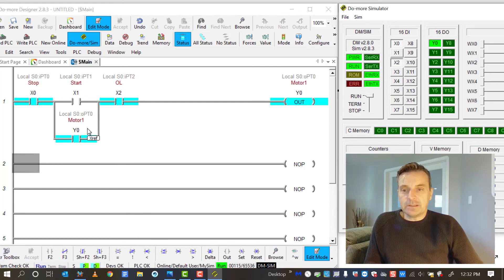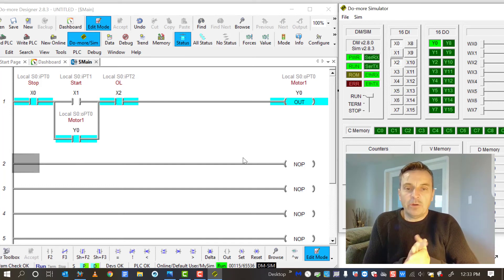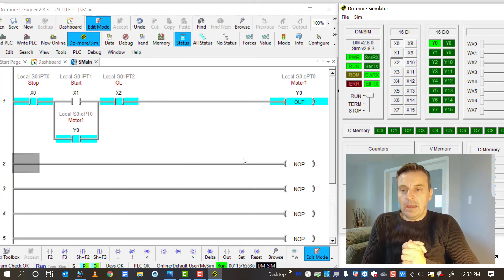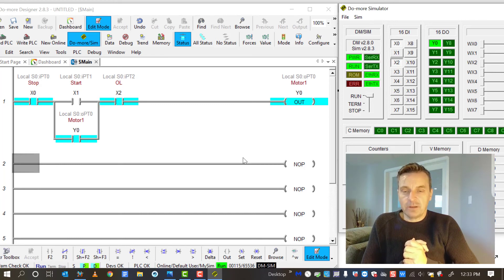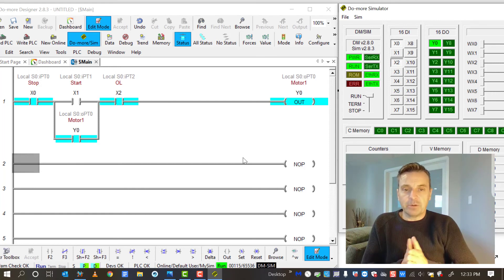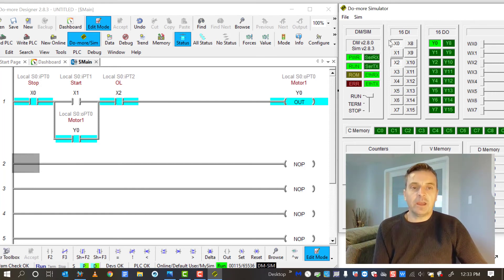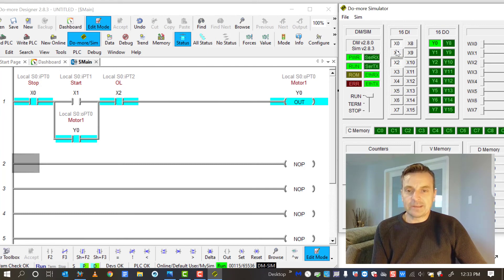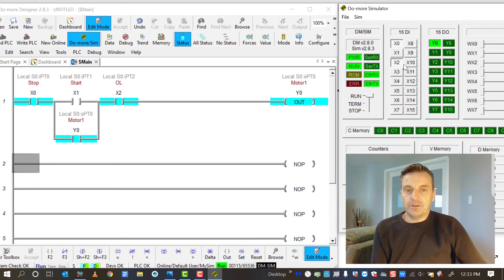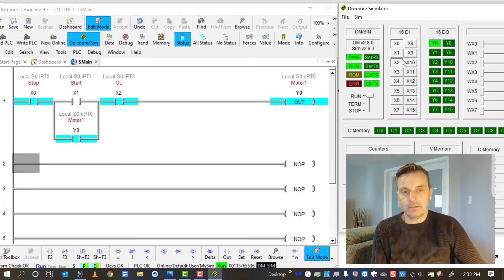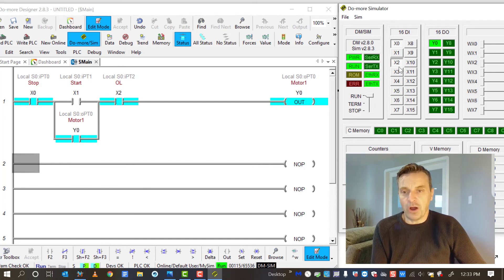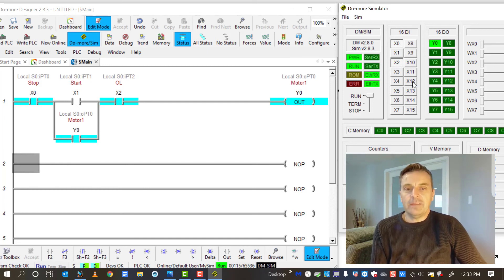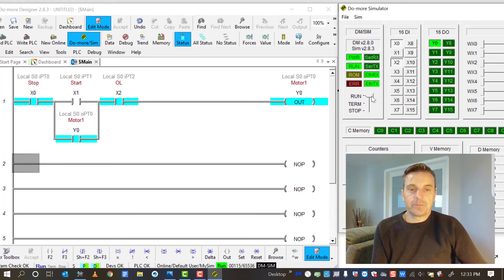And now I'll momentarily press X1 and take my finger off of it. And then you can see that it runs. So this would be how you would want to configure a three-wire start-stop station for a single motor control. And that's what it would end up looking like. Just remember you've got to think about your simulator and operate these buttons like they would be in the field. So if it's supposed to be wired to a normally open button, then leave it open. If it's supposed to be wired to a normally closed button or closed contact, close it. And then that will actually simulate what's actually happening out in the field.